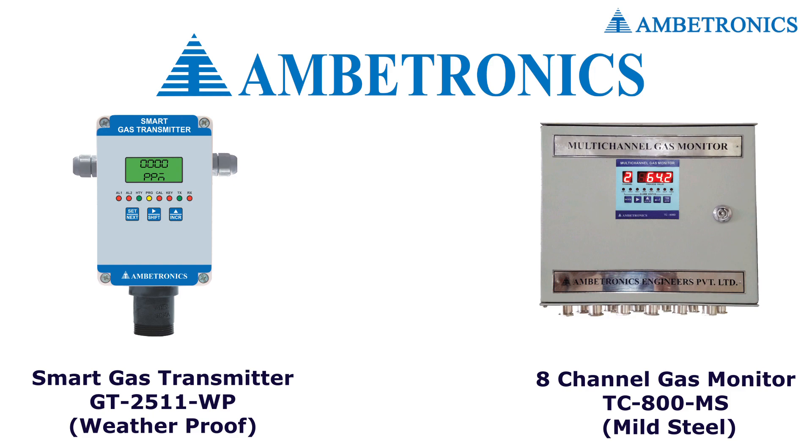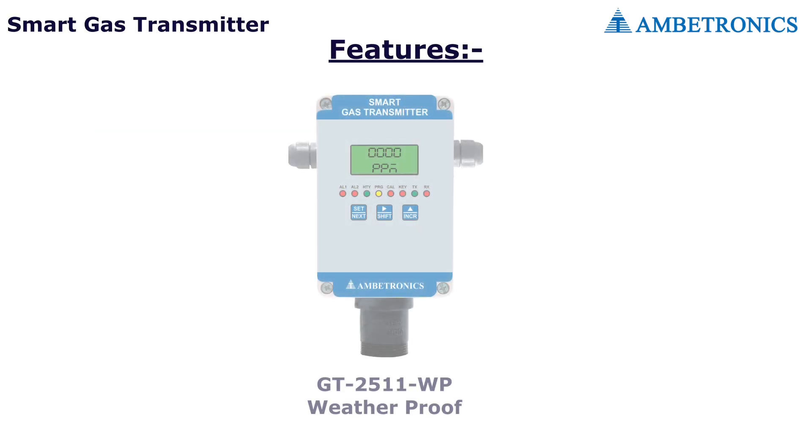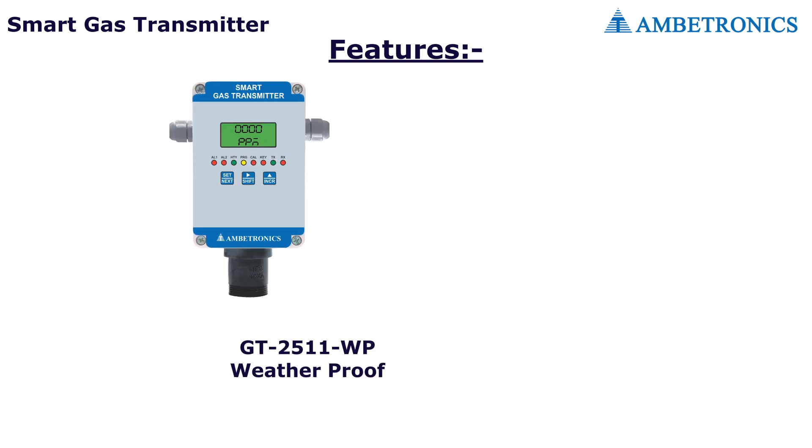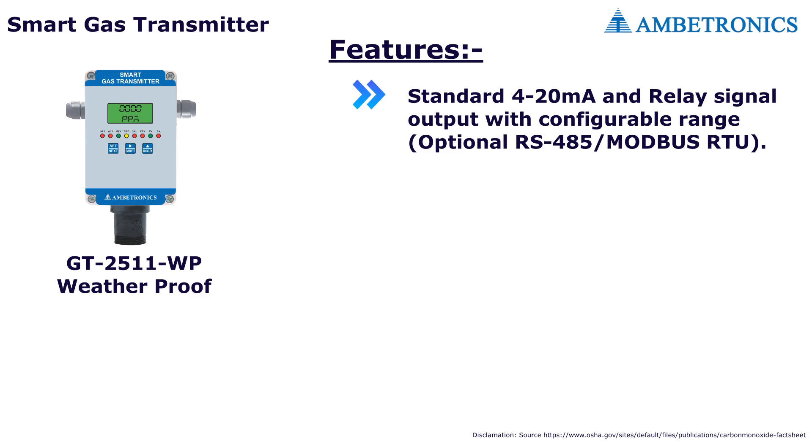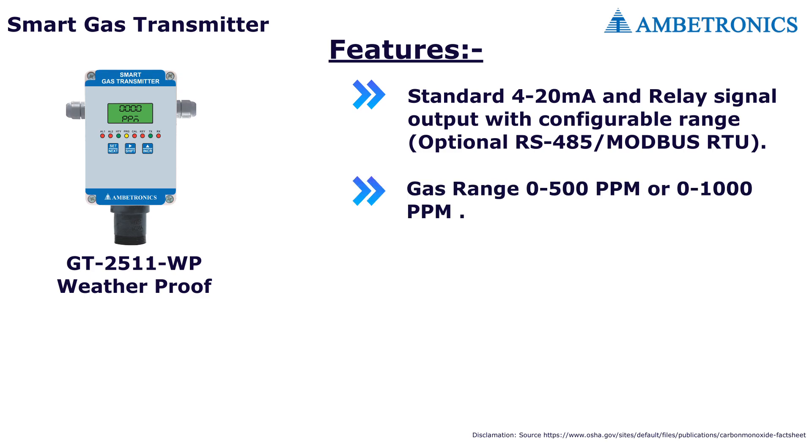And the 8-channel gas monitor TC-800-MS. Features of the GT2511: weatherproof detector for underground car parking, standard 4–20 milliampere signal output with configurable range. The gas detector is capable of detecting carbon monoxide concentration from 0 to 500 ppm or 0 to 1000 ppm.